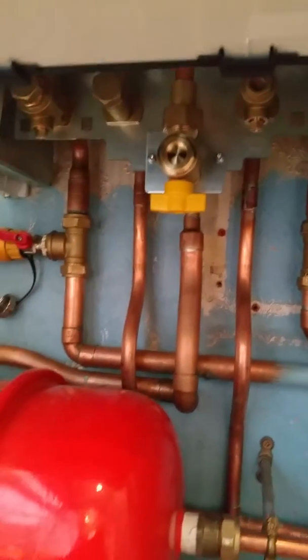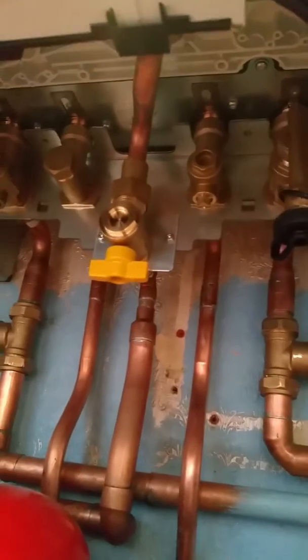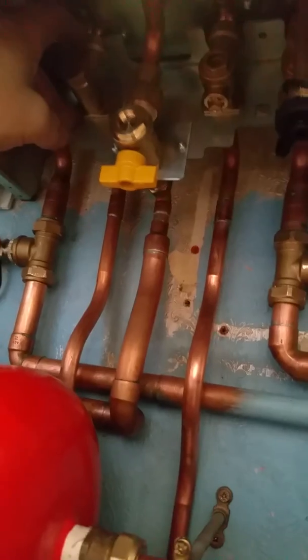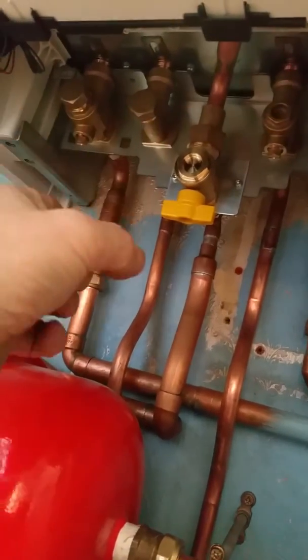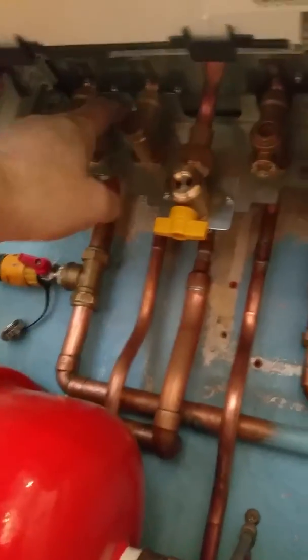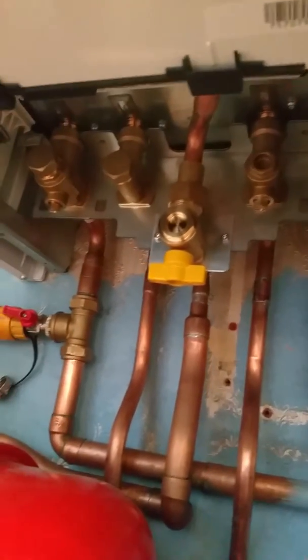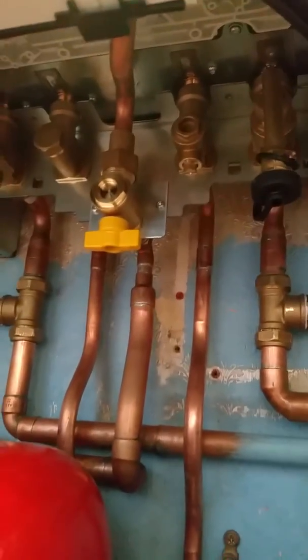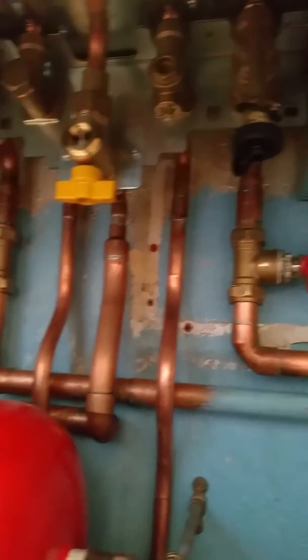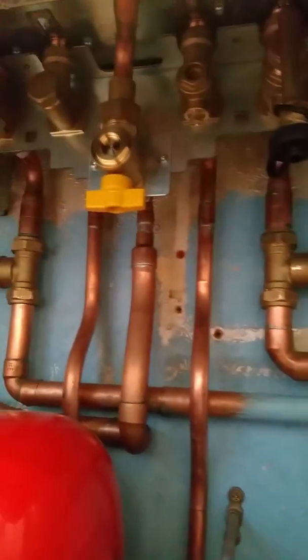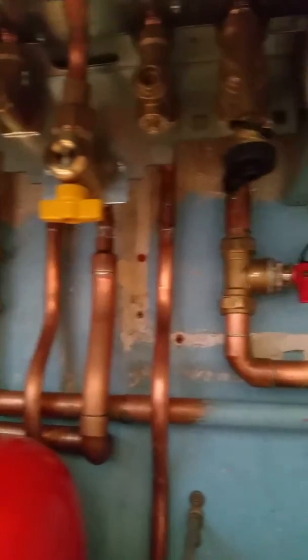New jig, brilliant, absolutely brilliant. I didn't used to use the other one because I found it horrible, but this one is brilliant. Just lift the boiler up, drop it in place. There's a widened recess that narrows down as it goes, and it just drops in on O-rings. So you lift the boiler on the wall, drop it in place, and it all slots in. You can pre-plumb with the wall jig, everything with the boiler out of the way, really nicely and easily, then just lift the boiler in place and it drops into place.